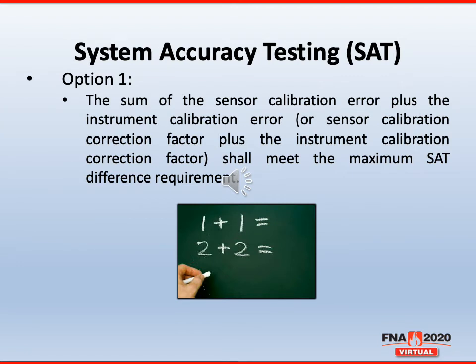Option 1, the sum of the sensor calibration error plus the instrument calibration error, or you can use the sensor calibration correction factor plus the instrument calibration correction, shall meet the maximum SAT difference. In other words, you're taking the calibration report from your process instrumentation and the calibration reports from the load thermocouples, combining them together, and as long as they're within the allowable SAT tolerance, that meets option 1 of the alternate SAT.